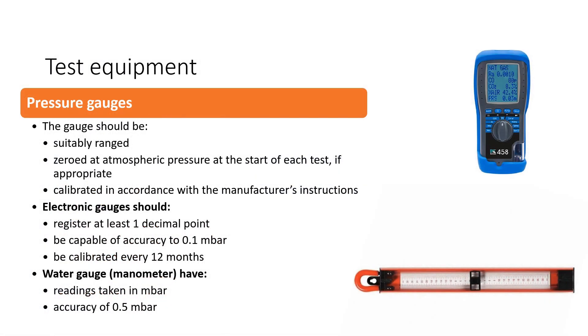Moving on to test equipment — there are two types: electronic and water gauge (U-gauge) type test equipment. Regardless of which type you use, they should be suitably ranged. It's no use using a U-gauge that only reads up to 10 millibars on a 20 millibar system, so they should be suitably ranged. They should be zeroed before use, and in the case of electronic gauges, they should be calibrated in accordance with the manufacturer's instructions.